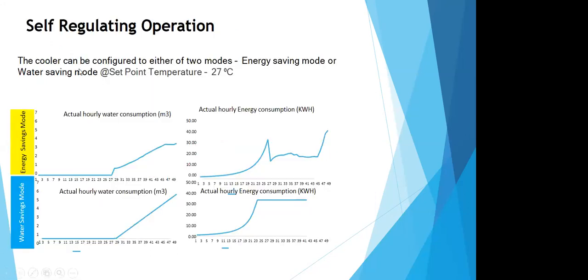So as I mentioned, the cooler can be configured in two modes, the energy saving mode or the water saving mode, depending on the set point temperature. So if you are working in energy saving mode, your fan will be optimized and the energy consumed will be minimized, while the adiabatic cooling will be working at the maximum condition. While in case of a water saving mode, the pre-cooling adiabatic feature will be reduced while the fan consumption would be maximized. So one can choose based on their requirements what mode they want to operate the unit at.